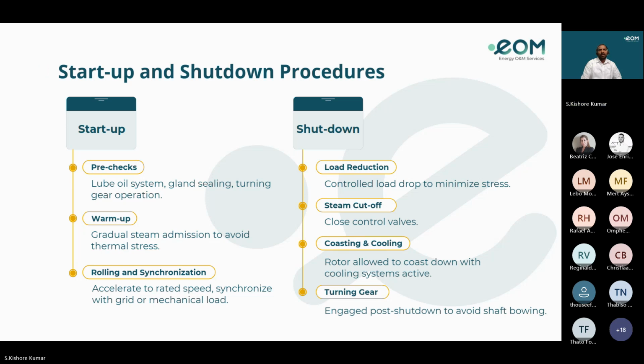Also, during turbine operation, check the time in idle speed of the turbine and the critical speed, whether it is crossing the critical band within the specified time, and also check the time during the coasting down of the turbine. Always be attentive while the turbine passes the critical band. For synchronization, it is always recommended to do it in auto. And when engaging and disengaging the turning gear, we always have to be more vigilant and careful.